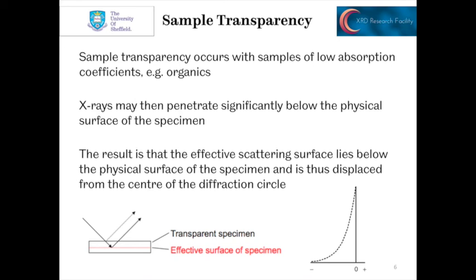What that gives you is an effective displacement away from the diffraction circle. And so we tend to see an asymmetry on the low angle side, because a good proportion of the sample is effectively too low. So it's kind of like a specimen height displacement error that is giving you that shift to a lower angle, or an asymmetry on the lower angle side of peaks.